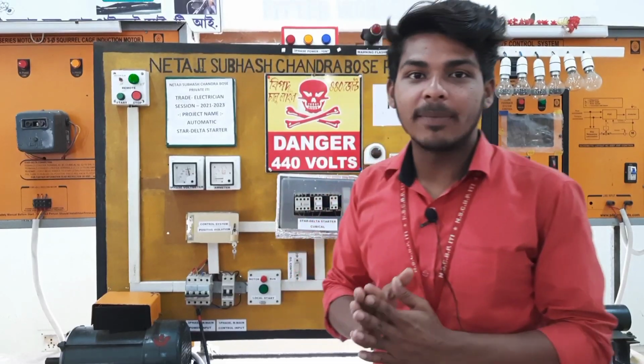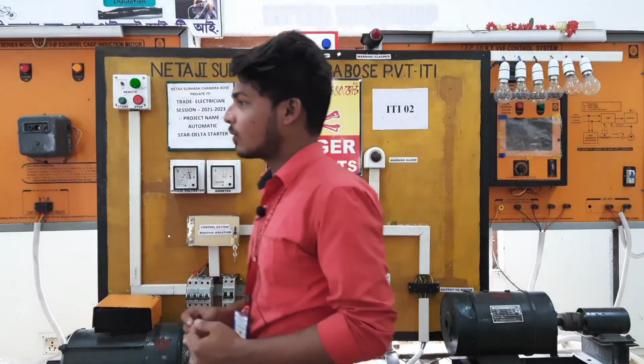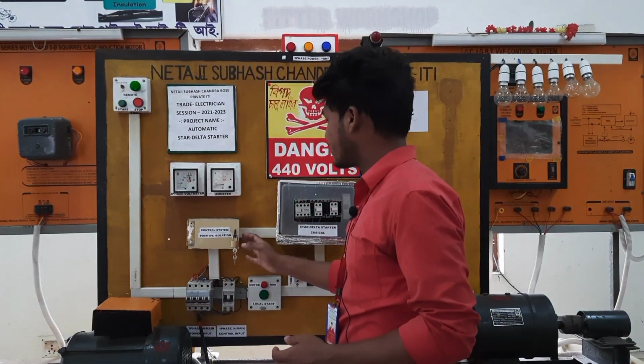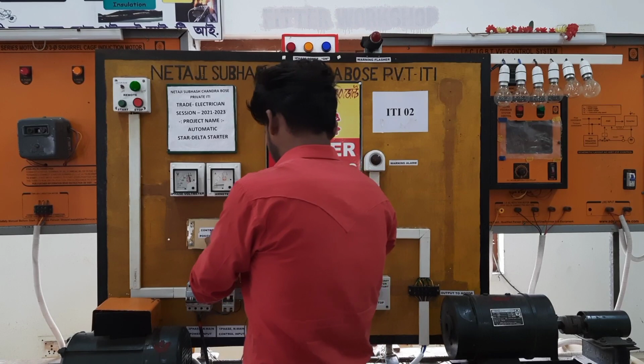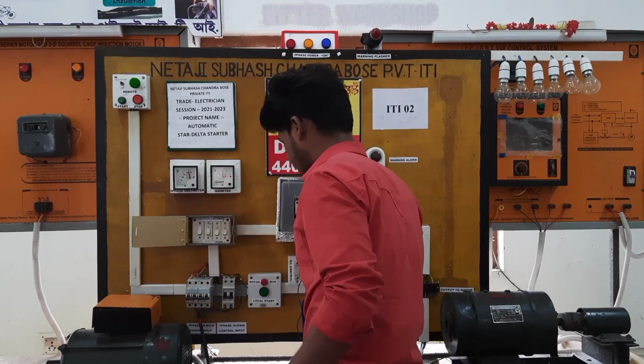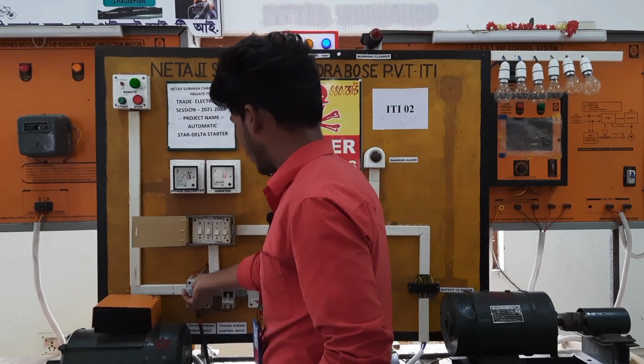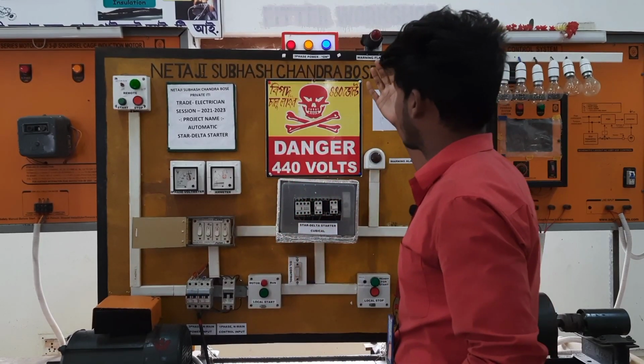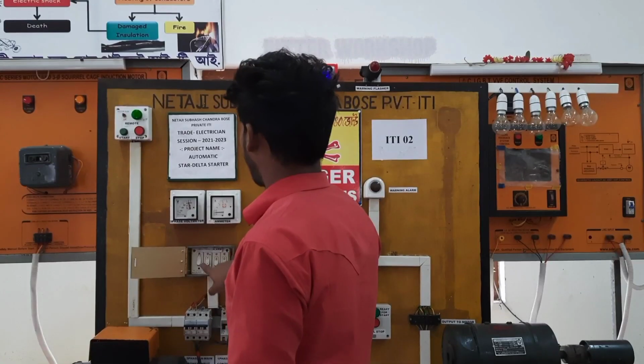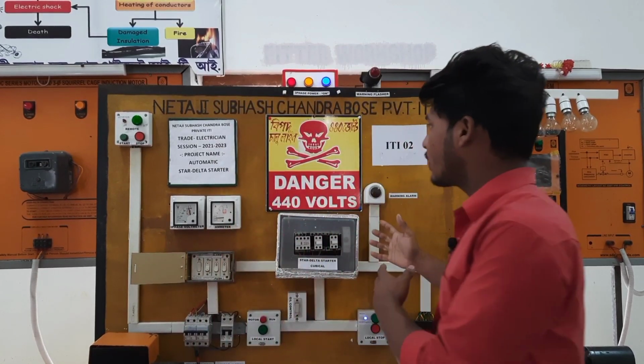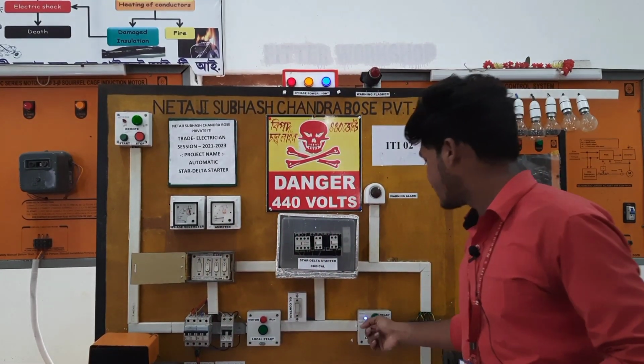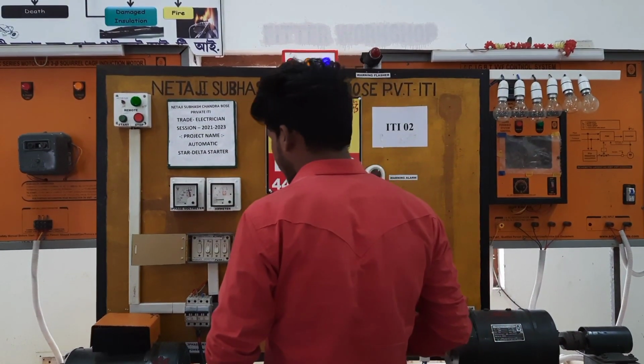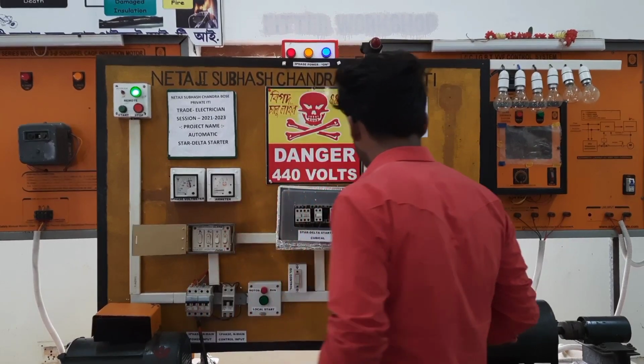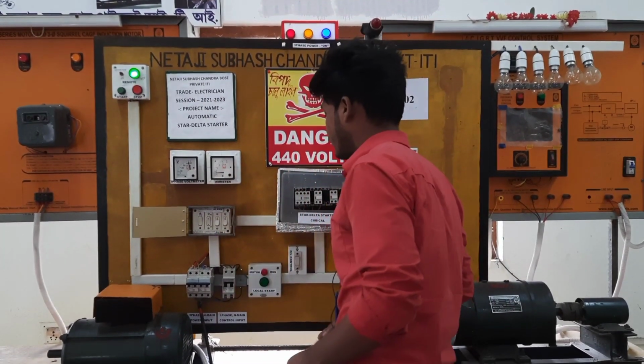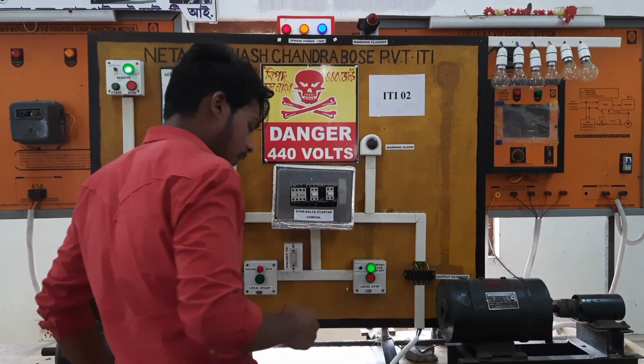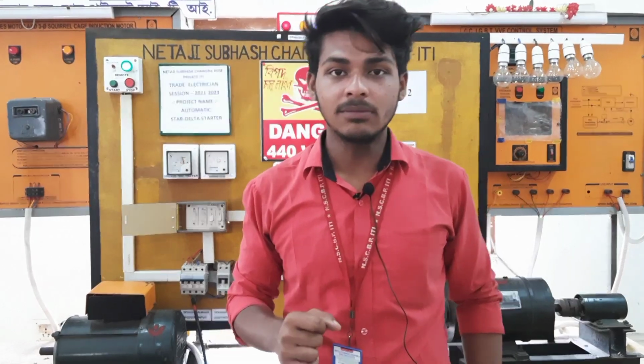Good morning. Today we have made an automatic star delta starter. At first the positive isolation is to be unlocked. Now control power and main power are on. Here the 3-phase power is available, and the 3-phase indication is on. Now control interlock on. Now our circuit board is in maintenance condition, and the maintenance indication is on. Now the mode selector should be in operation mode, and the indication is on for both remote and local. Now our motor is ready to start. For awareness purpose, we use audio alarm and the flasher.